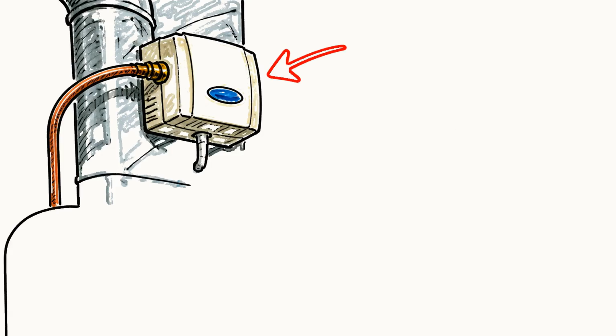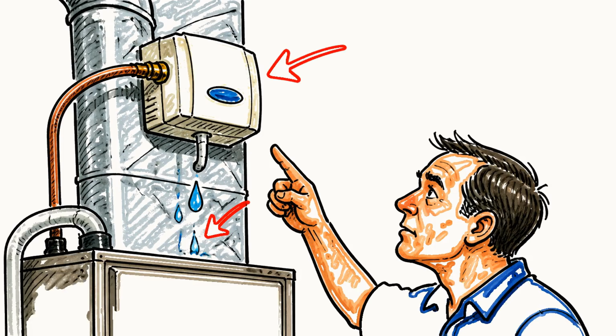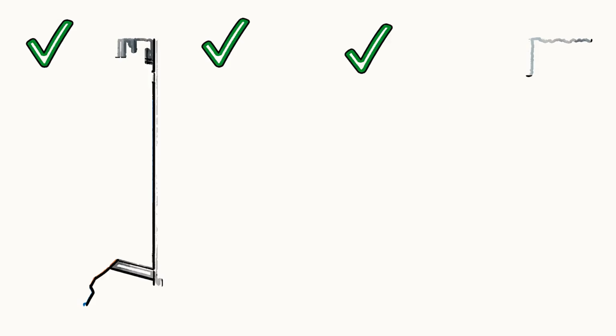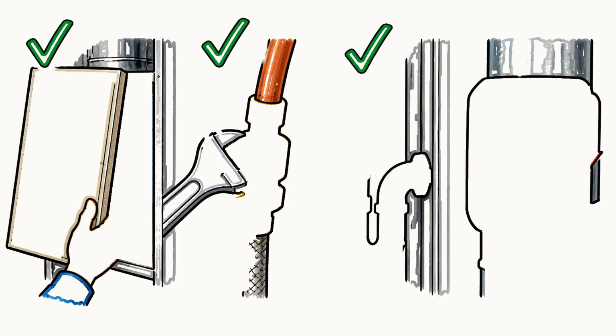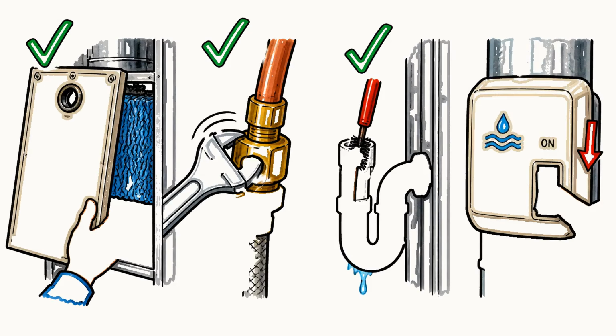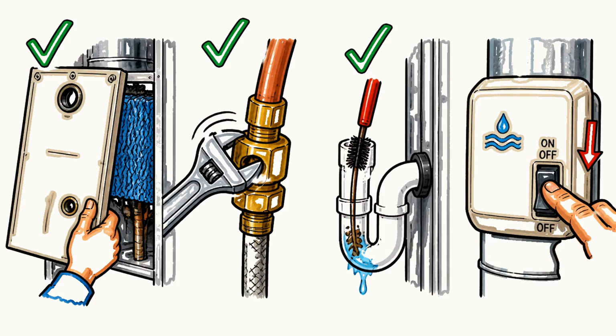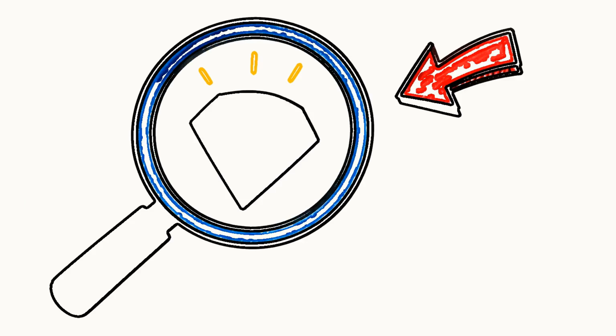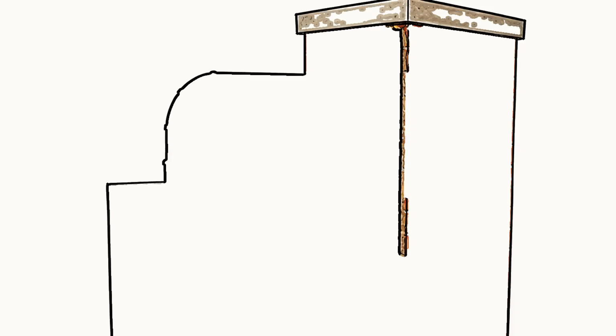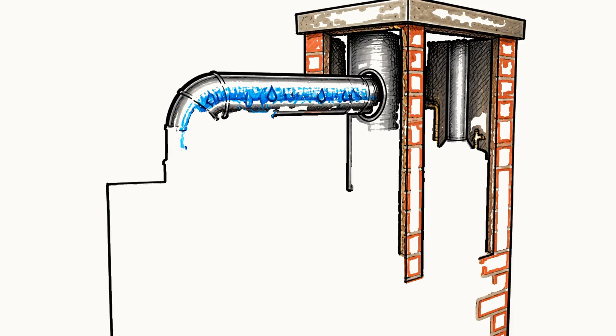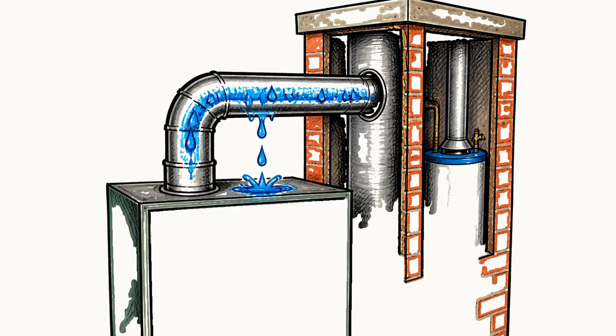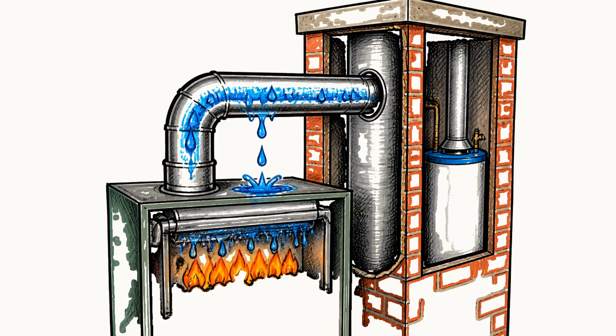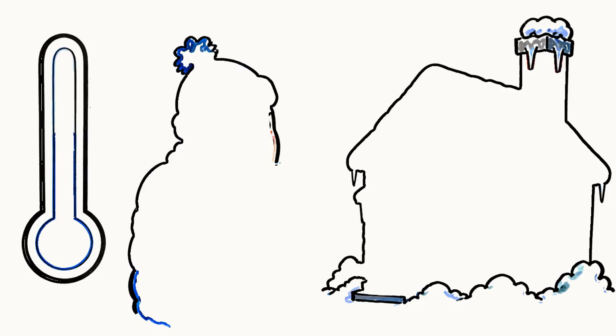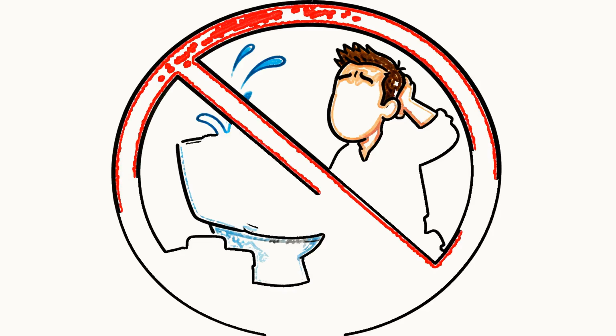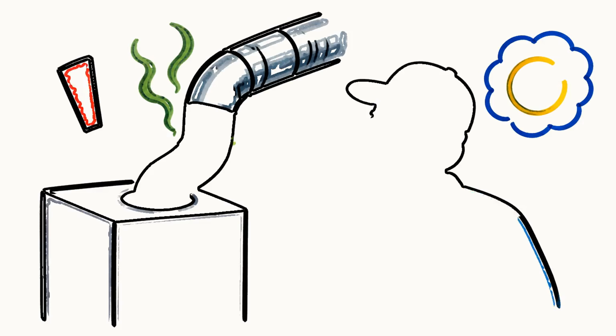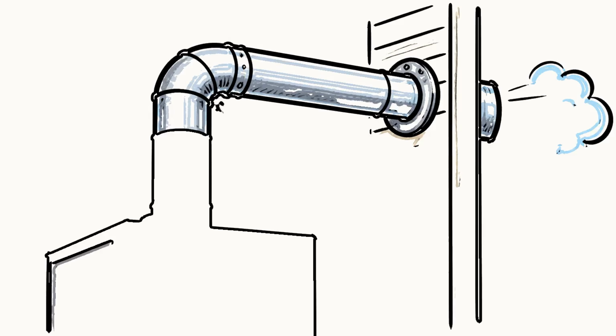Check whether the water is actually coming from that box up on the duct rather than the furnace itself. The fixes are easy. Replace the water panel, which runs $15 to $30, tighten or replace the supply line, and clear the drain. And turn the humidifier off in the summer when you do not need it anyway. The last one is less common but worth knowing. A standard furnace vented into a chimney that is oversized, cold, or shared with a water heater can let its exhaust cool down enough to condense inside the metal vent, and that water drips back down into the furnace. It tends to be worse in very cold weather. This is not a flush it yourself job. It is a venting problem, and you want a pro to look at how the furnace is vented.